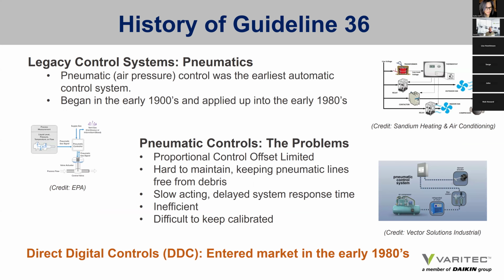The old control systems were pneumatic controls. They're still in existence in a number of old buildings today. They were the earliest form of control, and they were installed actually in the early 1900s. Pneumatic control systems used compressed air in the regulation of air to open and close actuators and devices. But they had some inherent problems. One, they had a limited range of proportional control and response. They were hard to maintain, keeping pneumatic lines free of debris. They were slow to act and had delayed system response time, were very inefficient, and they needed to be calibrated.